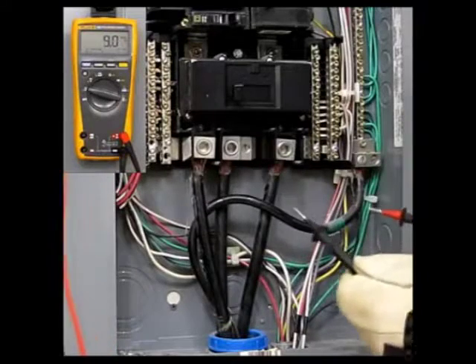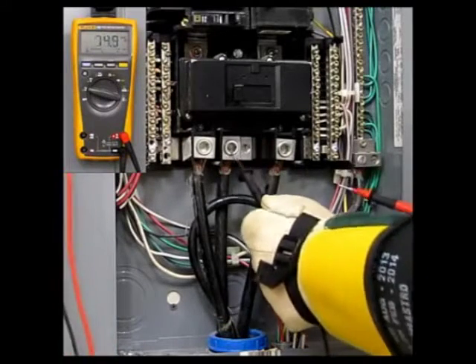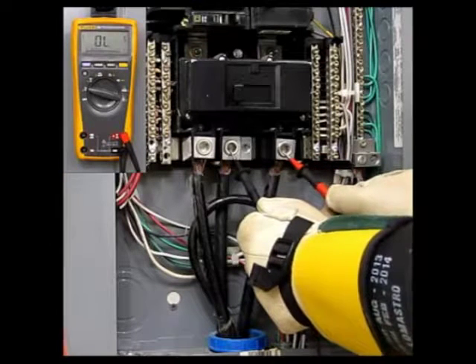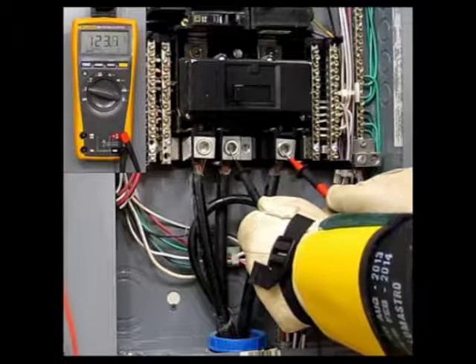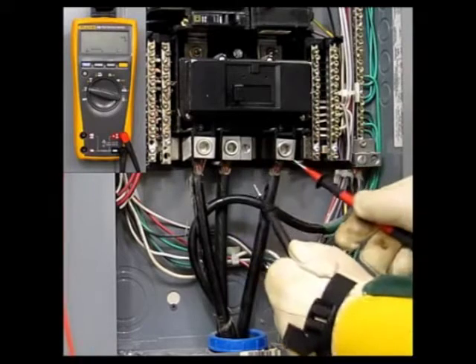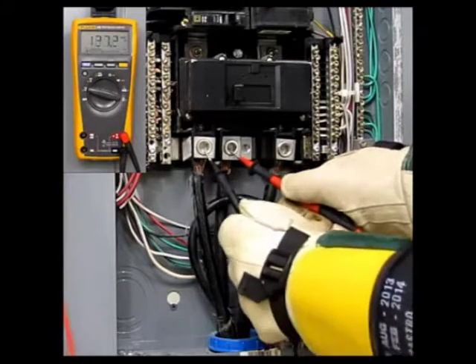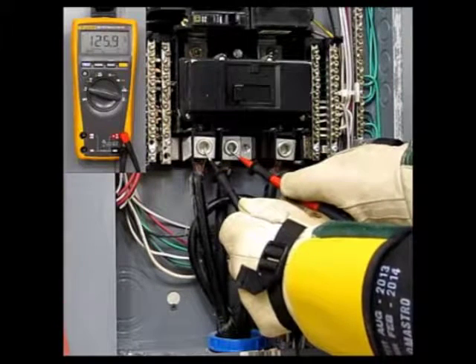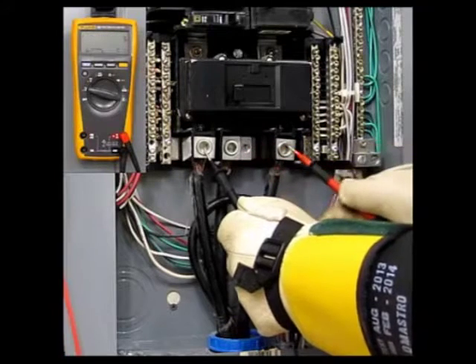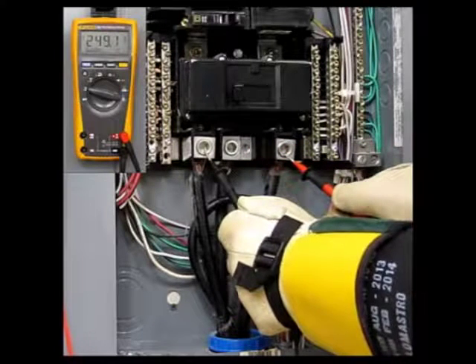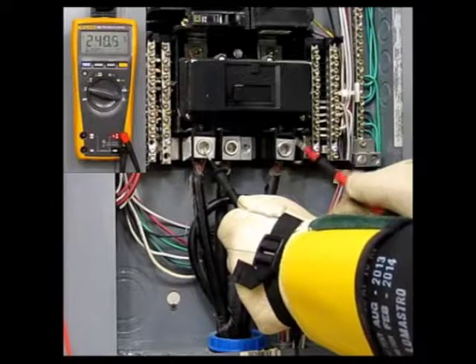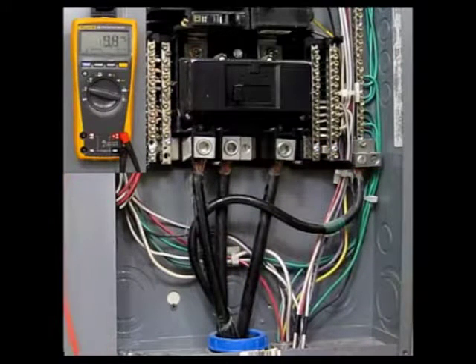Note that in the video, the electrician makes contact with the grounded conductor, otherwise known as the neutral, first, then makes contact with the ungrounded conductor, otherwise known as the hot, last. This is done because if the ungrounded conductor is made contact with first, then the other probe is energized and electricity is looking to complete a circuit home. He breaks contact with the ungrounded first and the grounded last for the same reason.